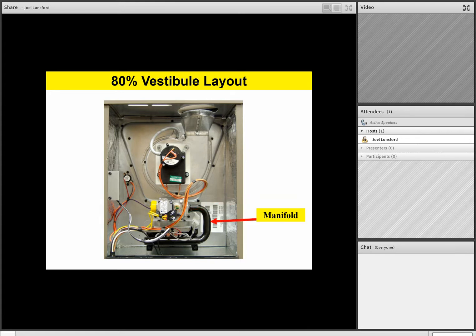Then we have our manifold assembly where we feed the gas to our manifold. And then we have our burner assembly, and please notice those burners are in-shot burners. This is very standard in the industry, and we feature in-shot burners on all of our furnaces. Near the burner assembly, you'll find a rollout switch. Now, we mentioned switches in our PowerPoint here because based on the size of the furnace, you may have one or more rollout switches, typically one or two based on the size of the furnace. You'll also notice that the rollout switch has a manual reset. This is a manual reset safety device.